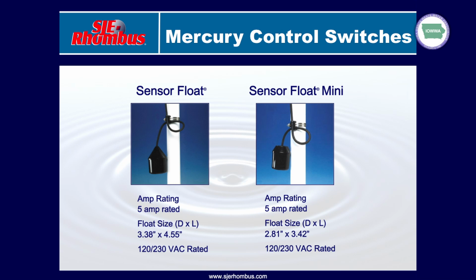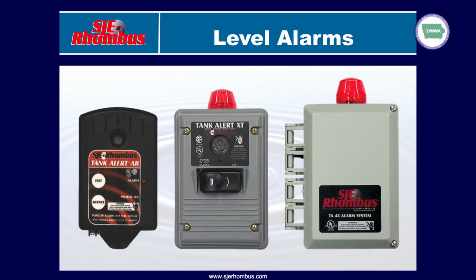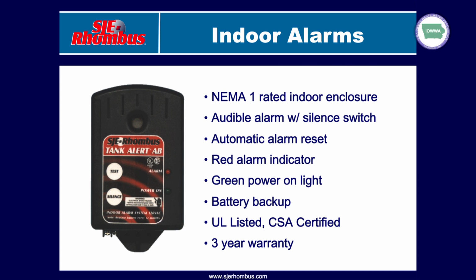All right, talking about level alarms a little bit. We're going to have really 2 different styles of level alarms, and whether it's a low level alarm or a high level alarm, we're going to offer them in an indoor version as well as an outdoor version. Some of the things I would recommend that you look for if you do sell your customers high level or low level alarms. On the indoor alarm, some of the things that I think should be standard features on your alarm, if it's a NEMA 1 rating, it's not rated to go outdoors, so it's going to have to be an indoor installation. The audible alarm with a silence switch is a good idea.